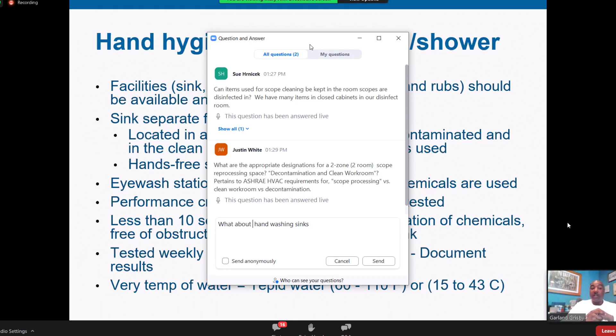Your eye wash should not be in a decontam sink either. And the temperature of the water—this may be an engineering function in your facility, because they have to test and make sure it meets requirements for comfortable flow and temperature. We do not want to have to use the eye wash and have the water too hot or too cold.